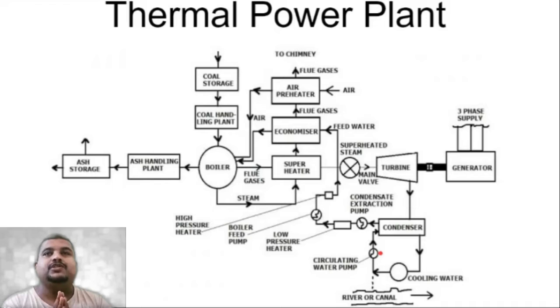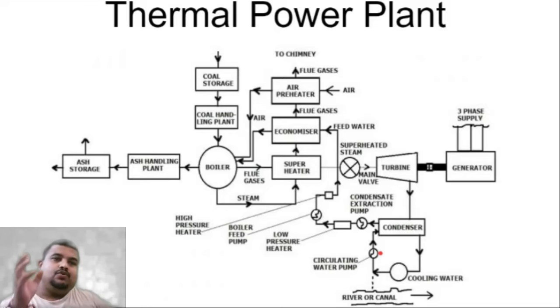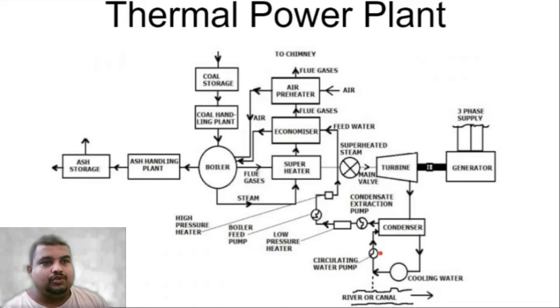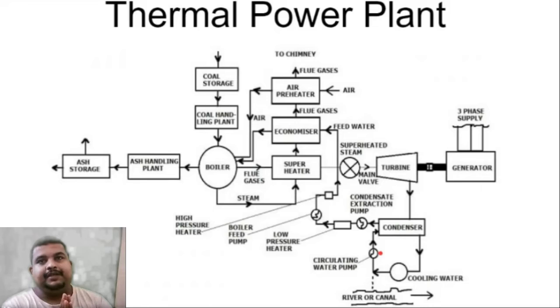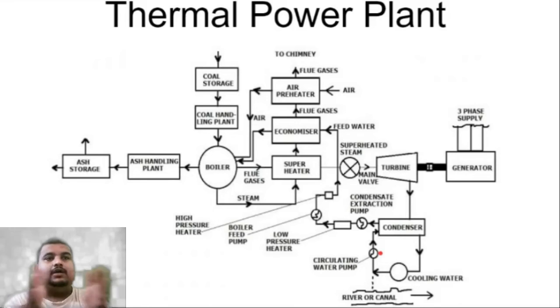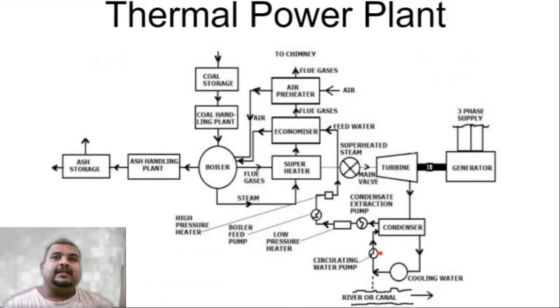Coal has to be stored for a minimum of 3 months of operation. After that, we separate the coal from its unwanted parts. In the coal handling plant, there is a magnetic separator and size-based separators for coal segregation. The coal handling plant also has a coal mill, which crushes the coal. This crushed coal is then stored in bunkers — bunkers are containers that store approximately one day's worth of coal for operation.